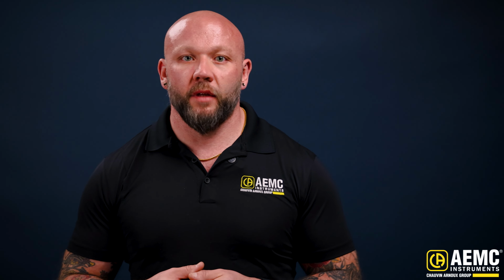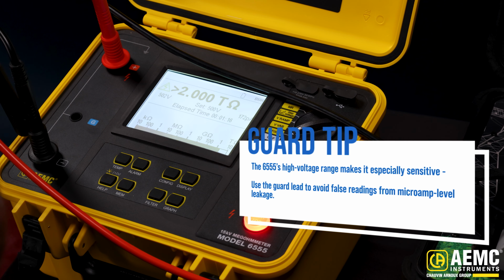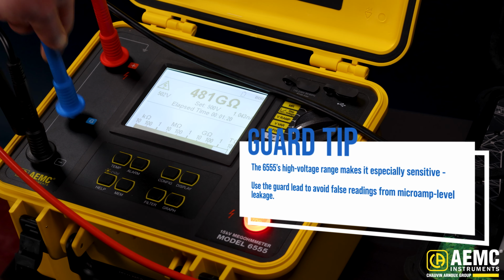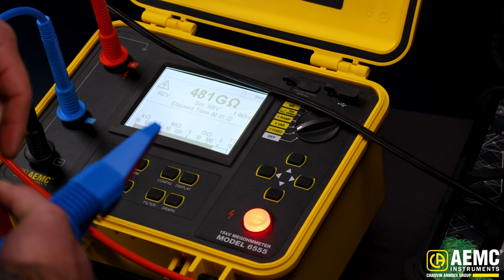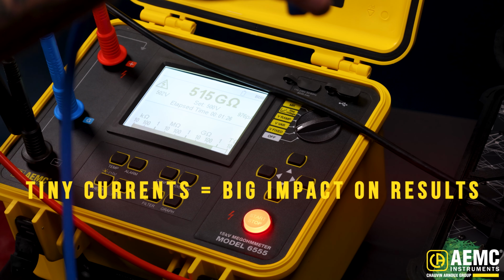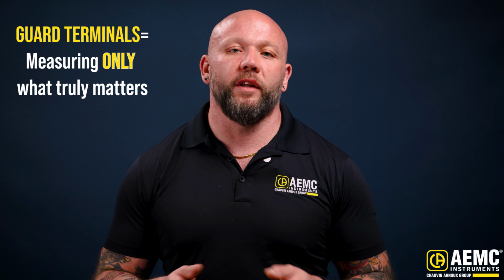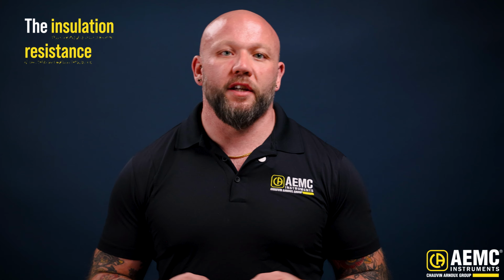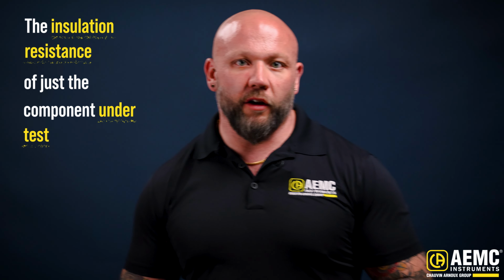measurement circuit. The 6555 insulation test instrument can test up to 30 tera ohms at 15,000 volts. And at those levels, even tiny currents on the surface can throw off your results. Using the guard terminal ensures you're measuring only what truly matters, the insulation resistance of just the component under test. Let's take a look at the difference.